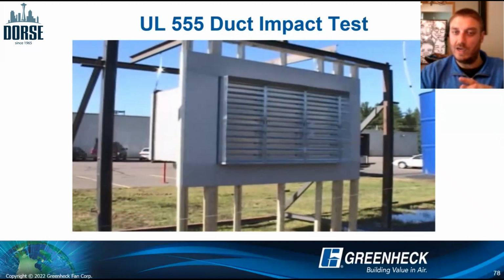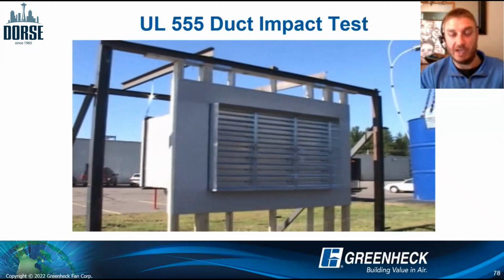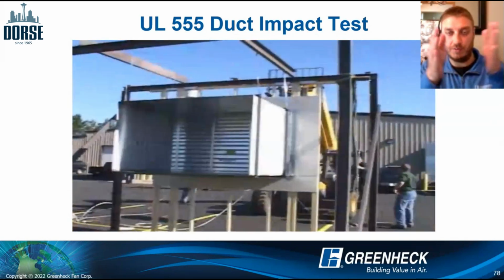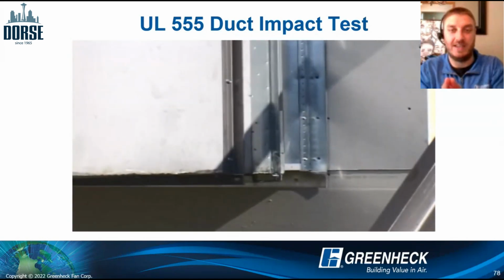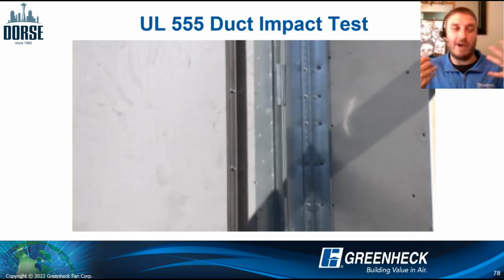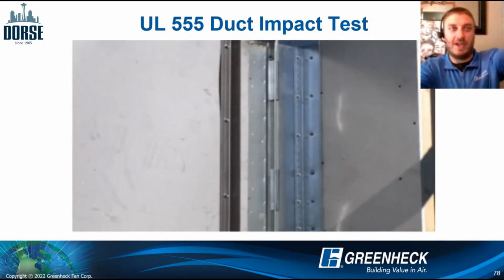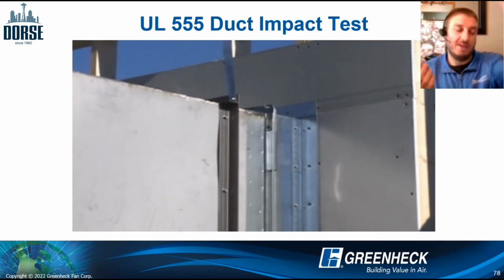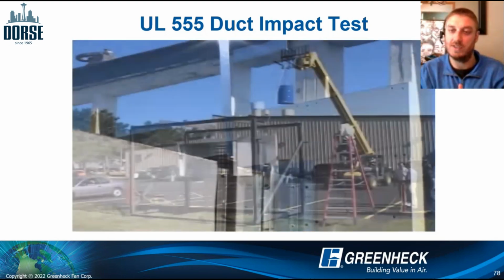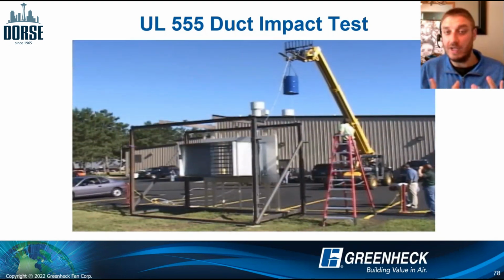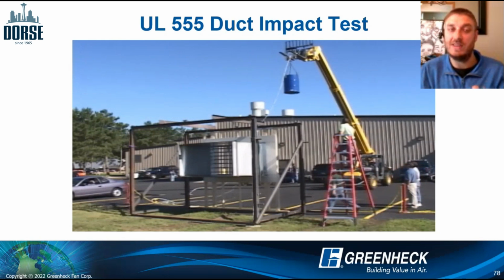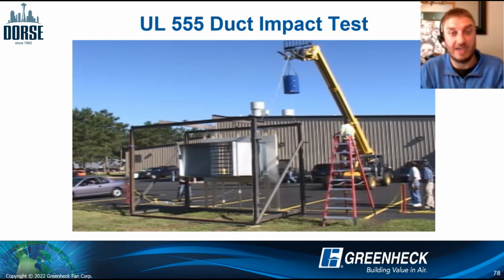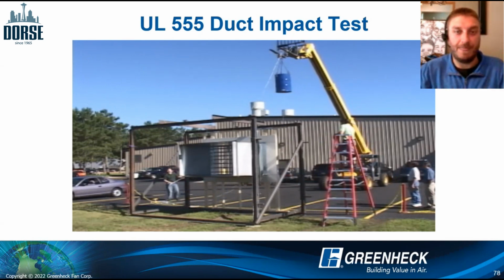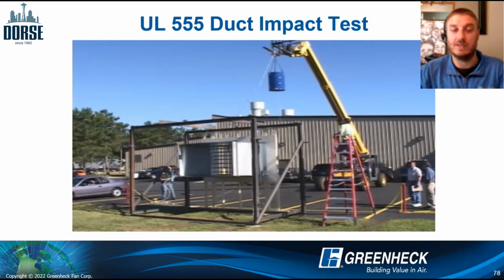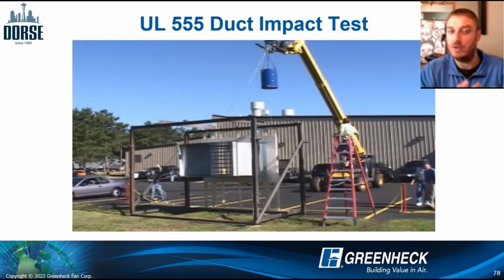Essentially, the whole reason you have to use these breakaway connections and terminate the ductwork at the damper is this: if you have a fire on a floor above you, you start having falling debris, something like that. If something falls and impacts your ductwork that's attached to your damper, you don't want that damper to be compromised. You still want that damper to remain installed in the wall and provide fire and smoke protection if necessary, and maintain the fire resistance rating of the construction it's installed into.